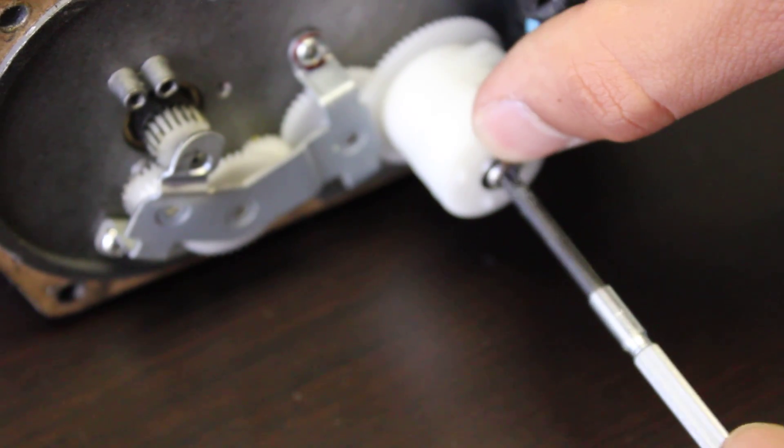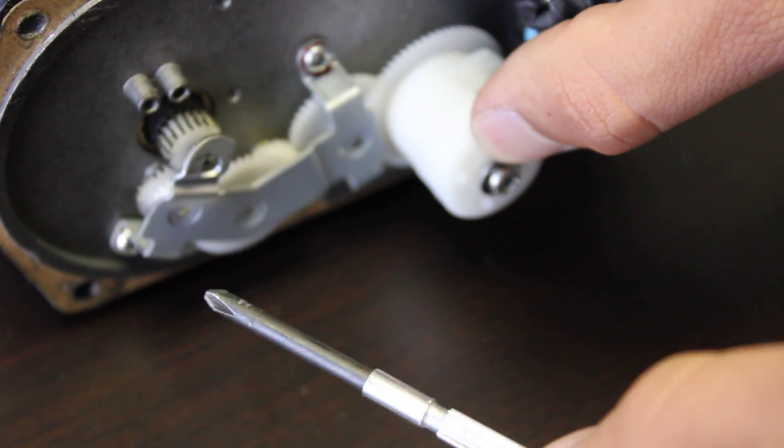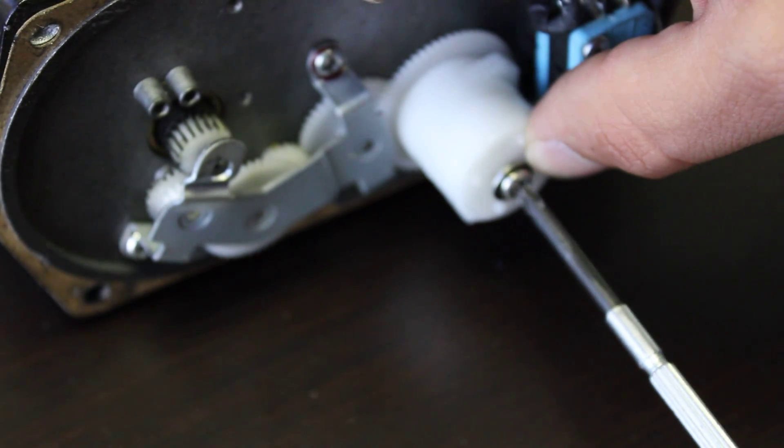So if you want to change the location of the limit switch, all you would do is unscrew here. You want to make sure, depending on which one you want to change, you hold down the other one so you don't mess up that position. You pull it out, adjust it, push it back in, and then re-screw it back in.